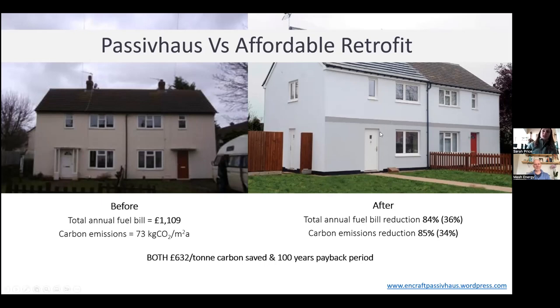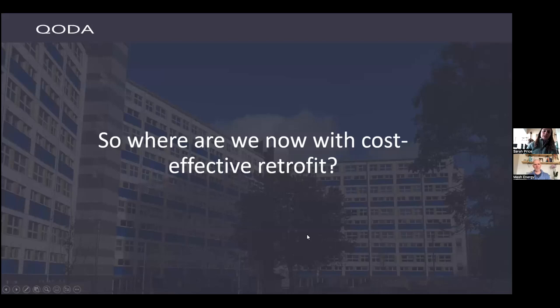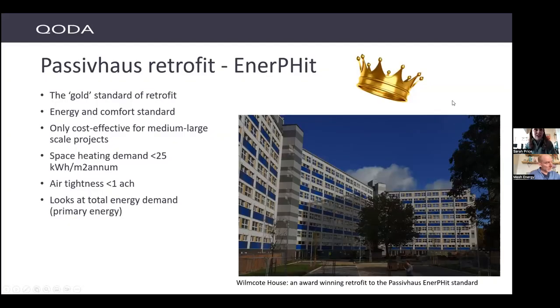Let's look at what we're doing now in terms of cost-effective retrofit in the UK. We've just looked at Passive House retrofit and EnerPHit. To go to Passive House standards you need mechanical ventilation with heat recovery, really airtight construction — less than 1 air change per hour (we're typically about 5 air permeability in domestic housing) — and a space heating demand of less than 25 kWh per metre squared per annum. It really is only cost-effective for medium to large-scale projects.